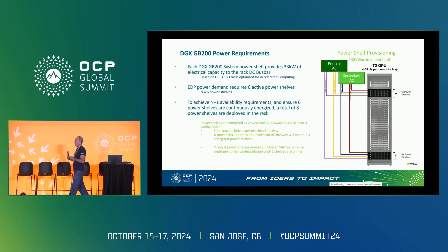A lot of people have A and B power. Because we've got eight rectifiers, you could power it four on A and four on B, but your workload might actually be harder than that. If you powered it with A and B power as you built out an AI factory in an existing data center, you might have degraded performance, but the software takes care of itself — the AI factory takes care of itself. The point is it can go in any data center we've got today.